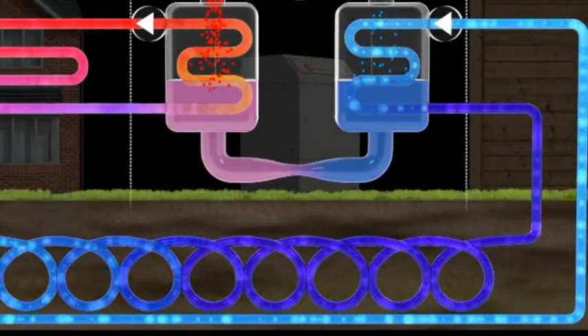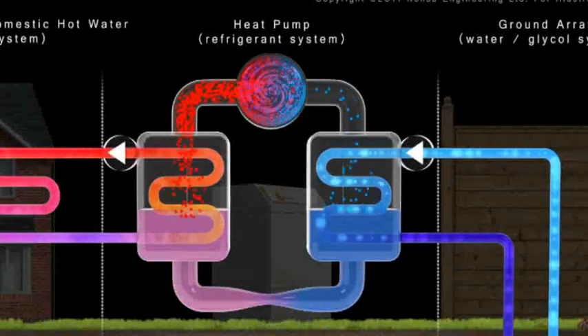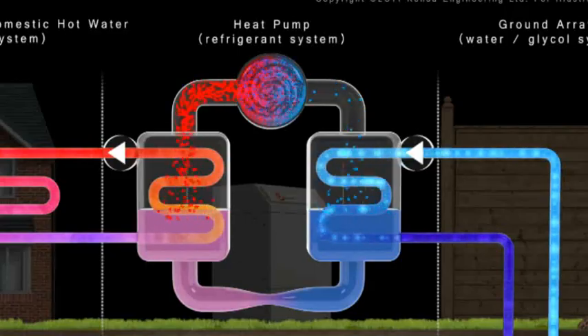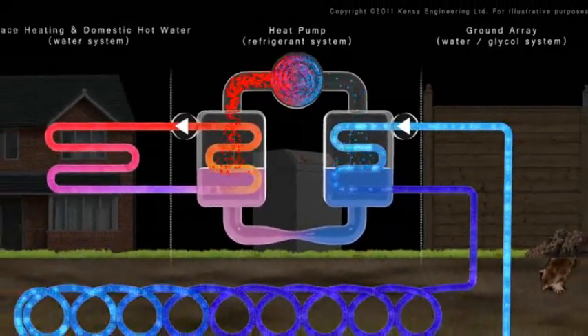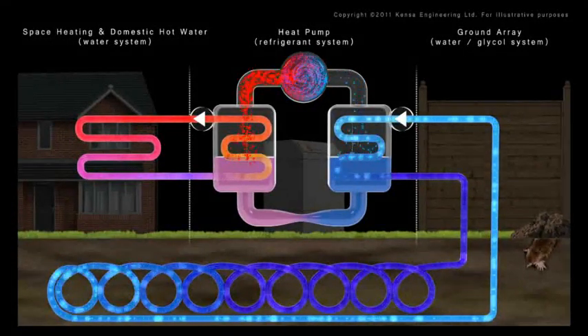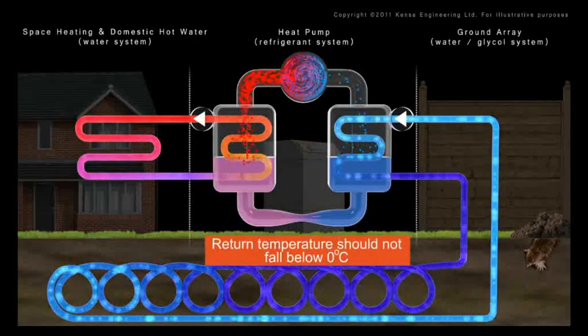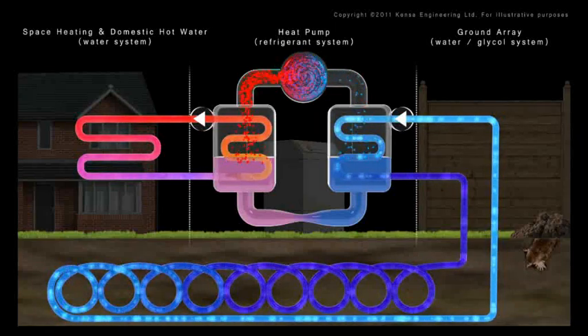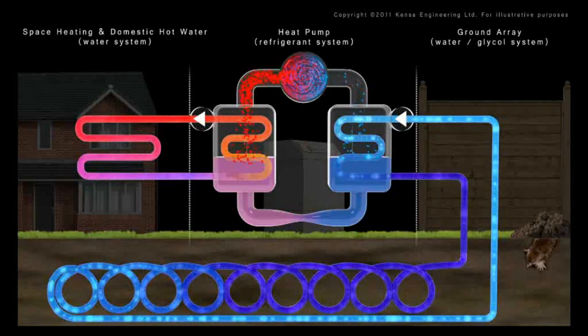Kensa's design wizard will ensure you deliver a sustainable ground array design, as undersizing a ground array can result in significant performance issues. If an excessive amount of energy is extracted from the ground, the fluid's return temperature to the heat pump will fall, reducing the heat pump's thermal capacity and its ability to maintain the required room temperatures. Lower return temperatures will also compromise the heat pump's efficiency. The MCS 3005 installer standard dictates the return temperature should not fall below zero degrees centigrade. If the ground array is too small and the energy is not adequately replenished, it will simply freeze and the system will require significant remedial work.